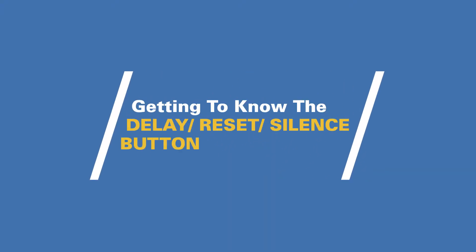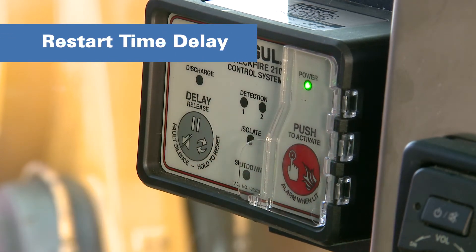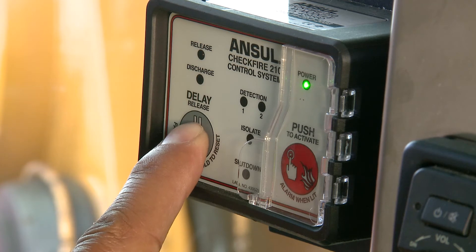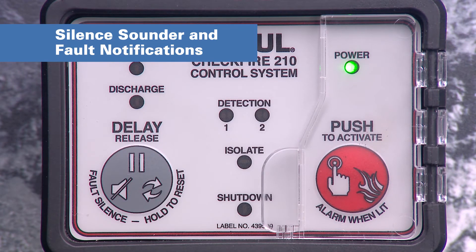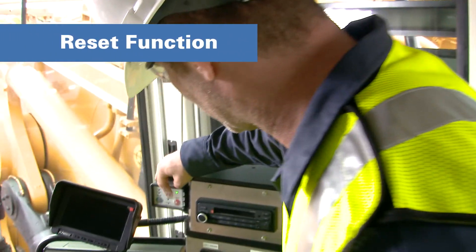The CheckFire 210 Control Module Delay, Reset and Silence button is specifically designed for easy use. Restart the time delay by pressing and releasing the button during time delay one — this must be initiated before the transfer to time delay two. Pressing down and holding it will not extend the time delay period, and be warned that delaying the fire suppression system activation may cause the fire to intensify. You can silence the sounder and fault notifications for two hours by pressing and releasing the button. The LED fault indication will continue until the fault is cleared, and any new fault or detection will reactivate the sounder. To silence the sounder during a post-discharge notification for two hours, simply press and release the button. The reset function is for an authorized Ansul distributor service technician.